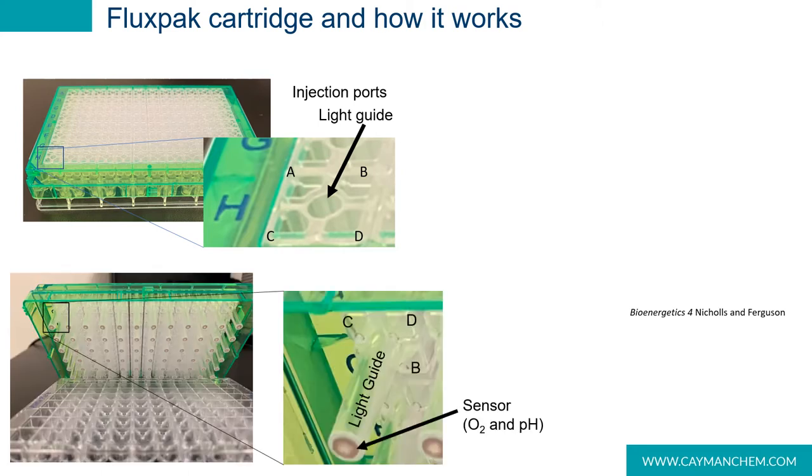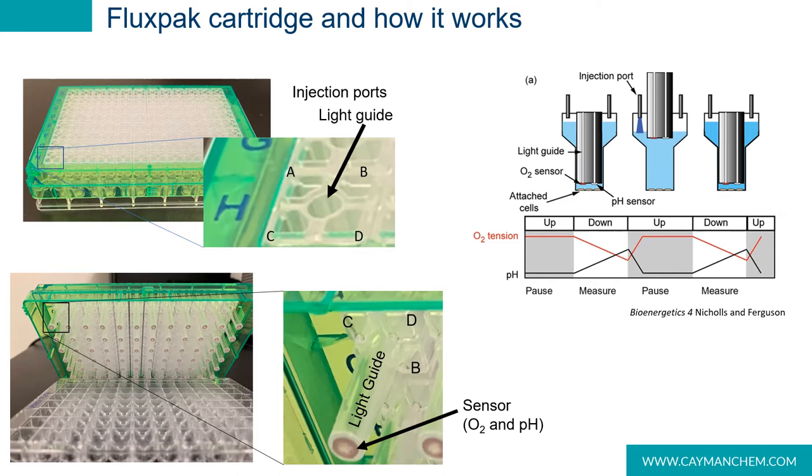The flux pack cartridge consists of two main parts: the sensor portion in green and the clear utility plate. An XFe96 FluxPak is shown on this slide. The upper portion of the sensor interfaces with the instrument and contains, for each well, four injection ports labeled A through D and a guide for each of the 96 probes that excite and measure the phosphorescence and fluorescence intensity of the oxygen and pH sensors. The piston-shaped lower portion of the sensor plate contains the oxygen and pH sensor and works in concert with uniquely shaped wells found in both the utility plate and the cell plate to create the measurement chamber.